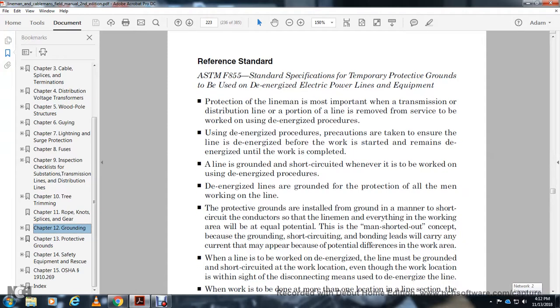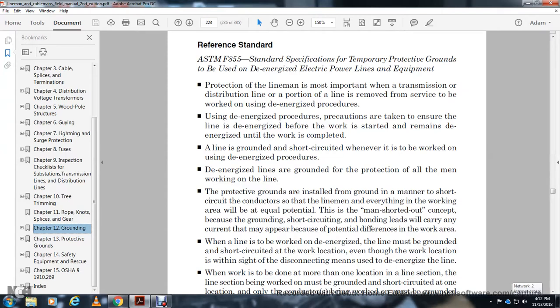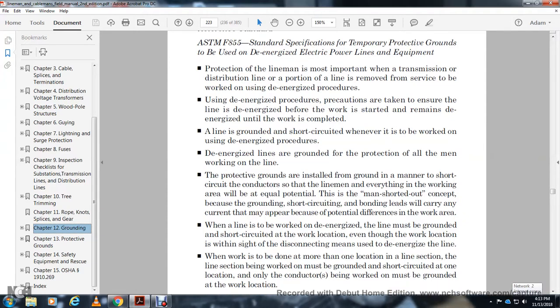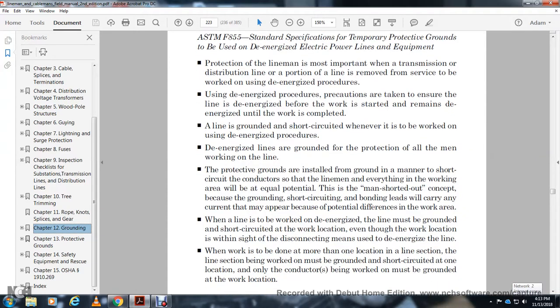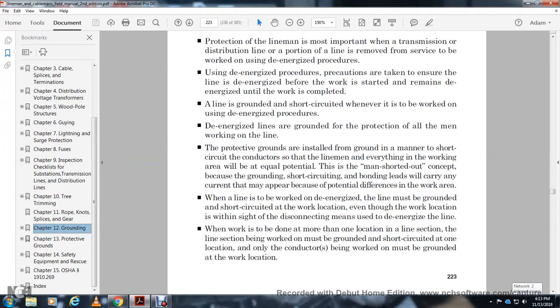When a line is to be worked on, the de-energized line must be grounded and short-circuited at the work location, even when the work location is inside of the disconnection points of the de-energized line. If working is done in more than one location in the line section, the line section may be worked on with the line grounded and short-circuited at one location. Only the conductors being worked on must be grounded at the work location.